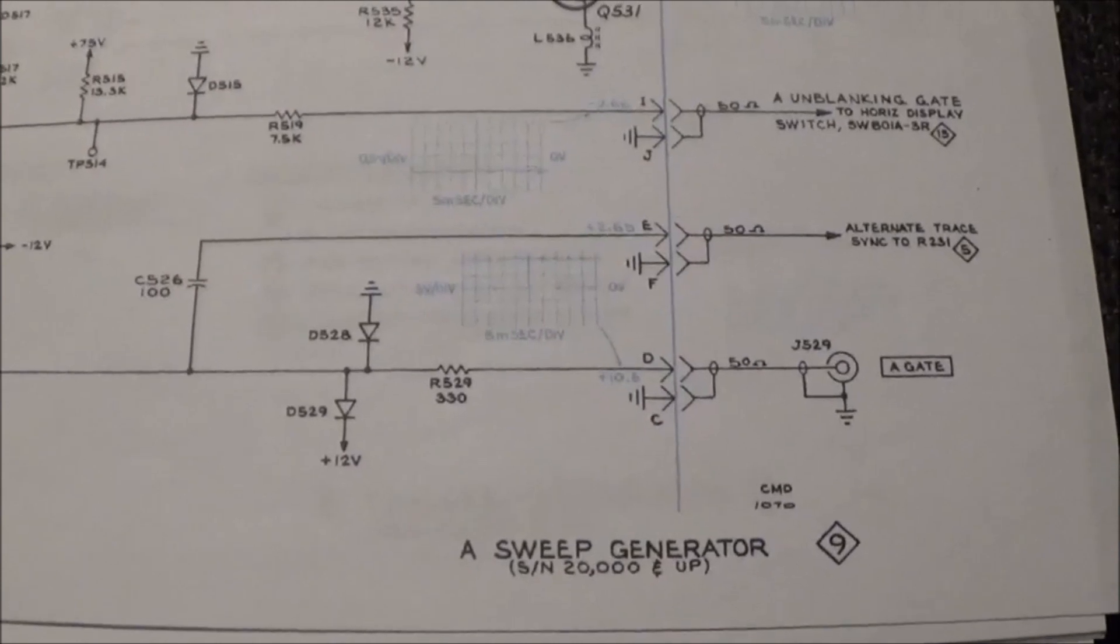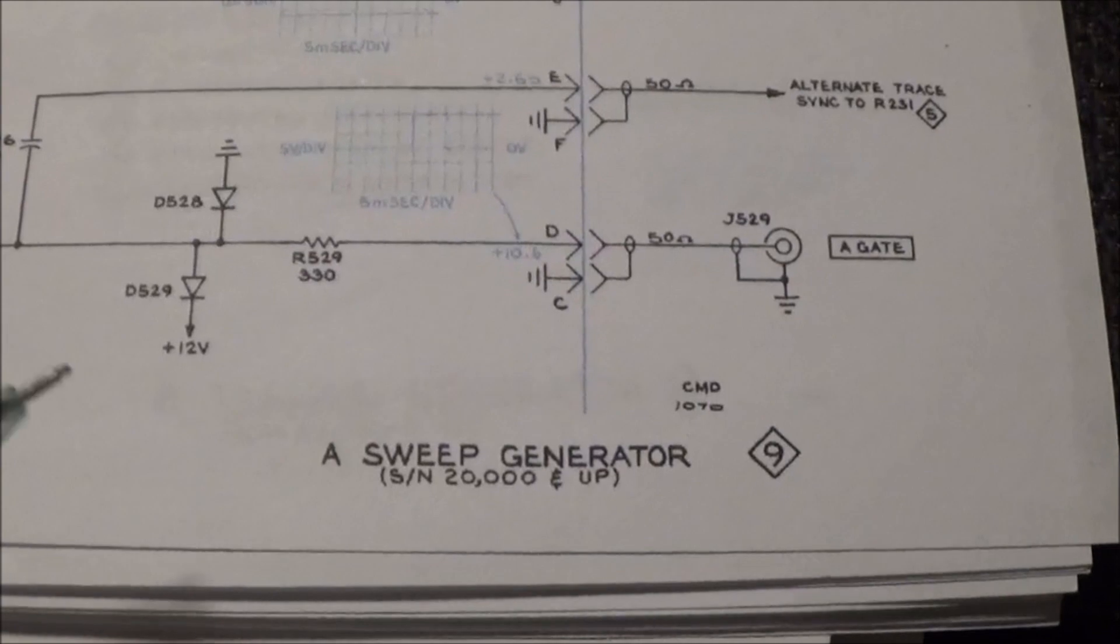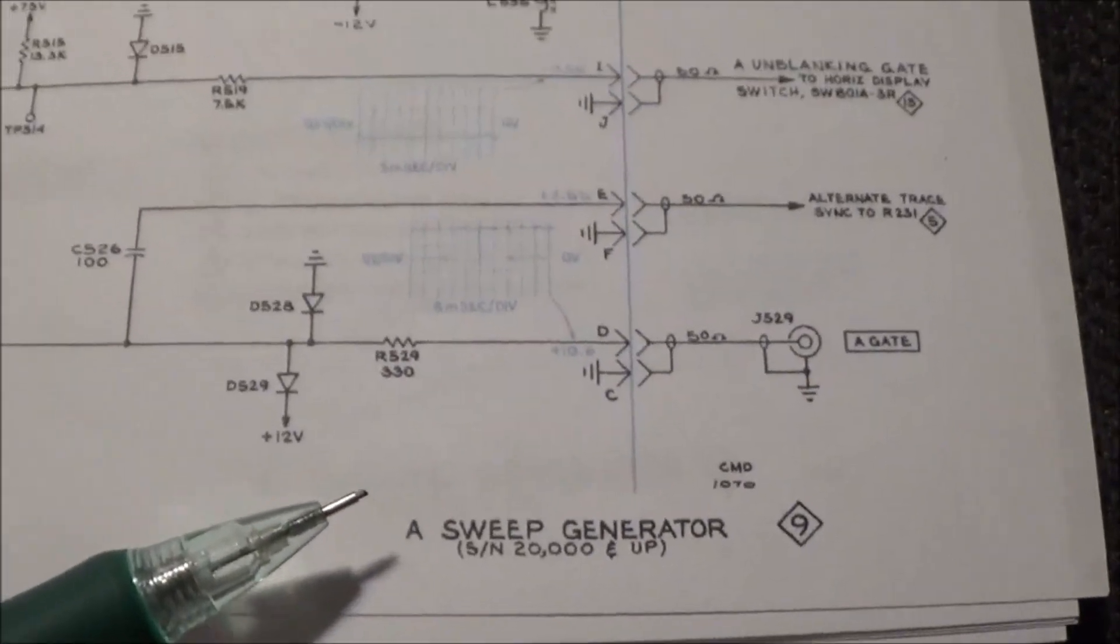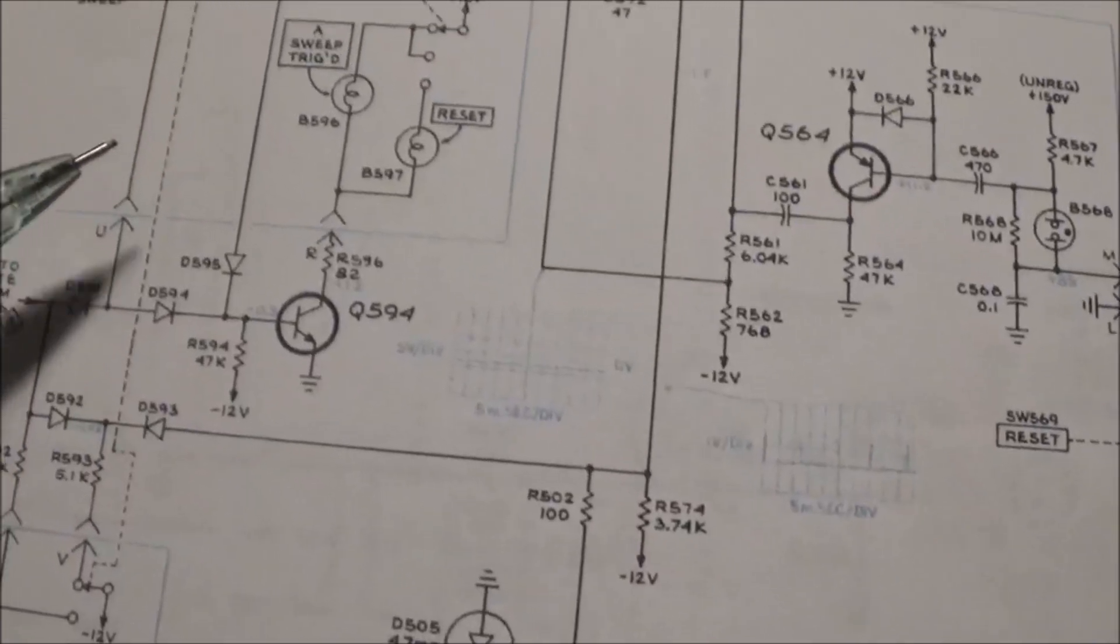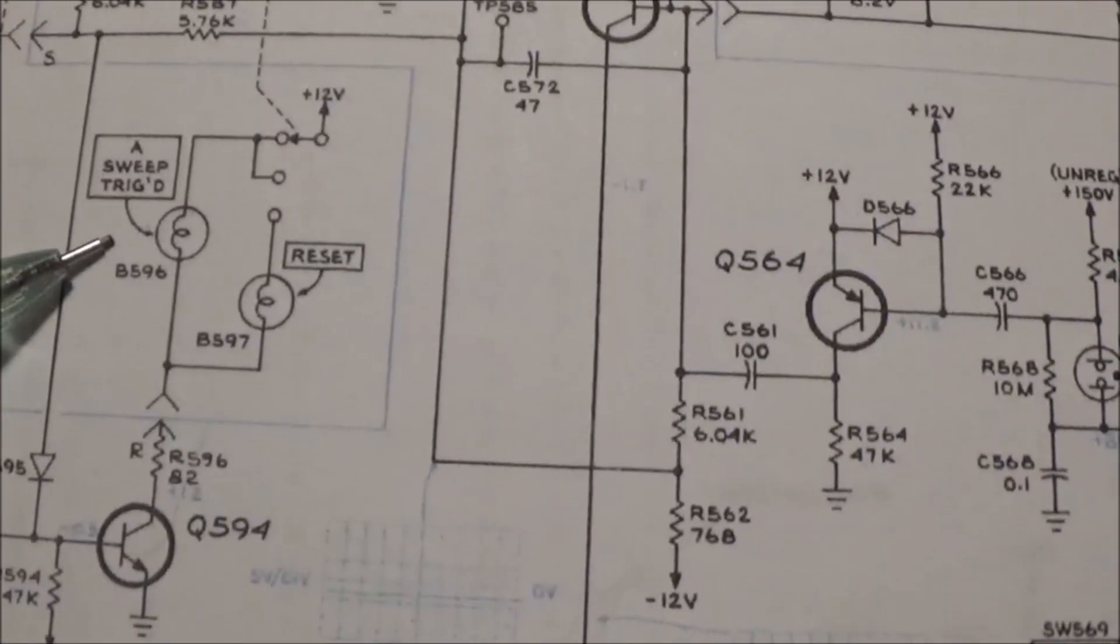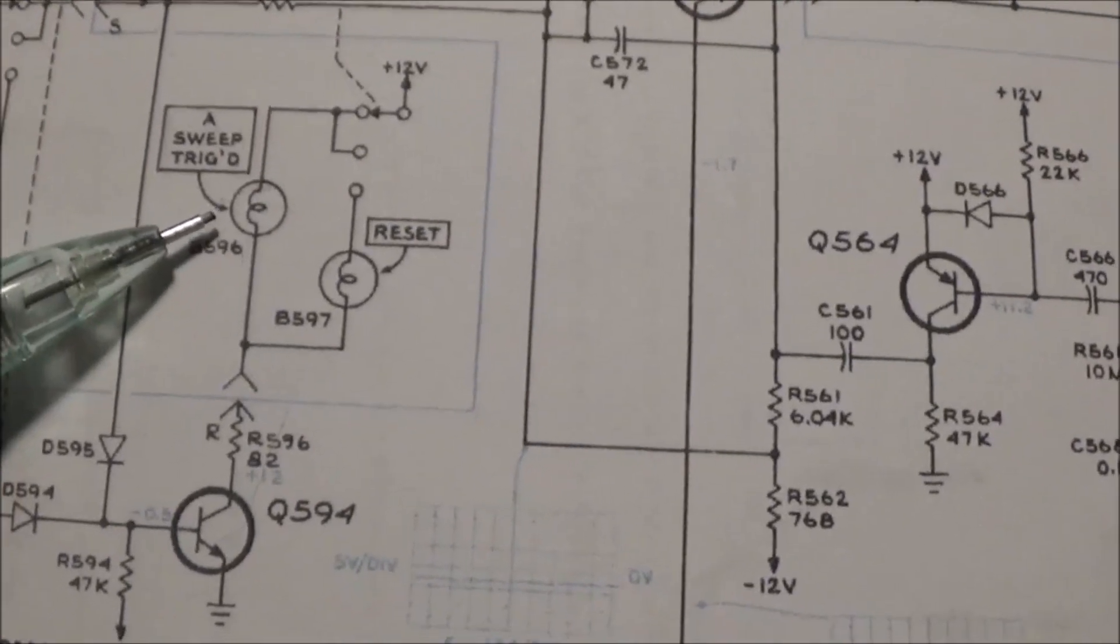Okay, so where this little bulb occurs in the circuitry is in the A sweep generator section. We're looking at the schematic here. It's right up here. This is it right here, B596, the A sweep triggered indicator lamp.